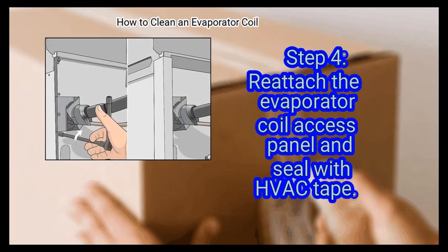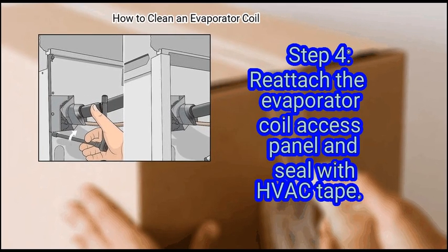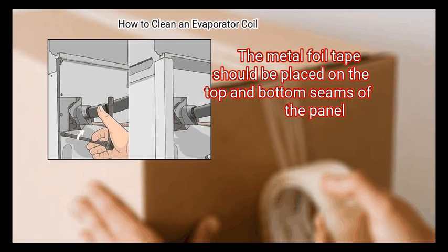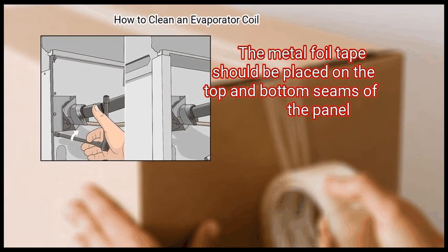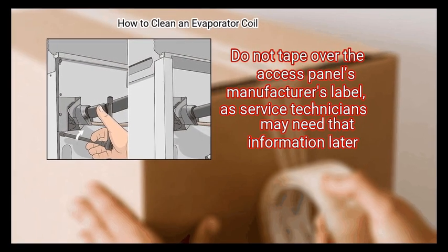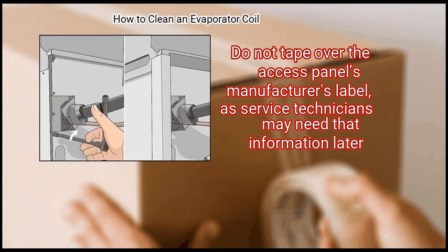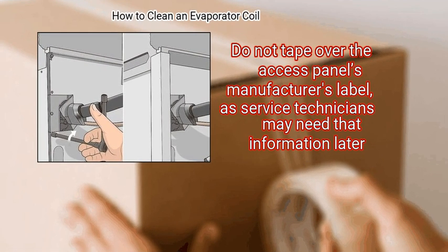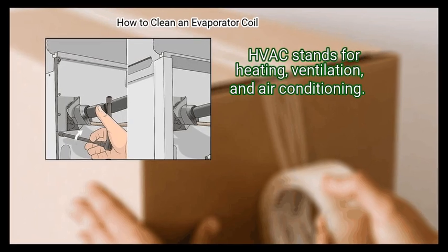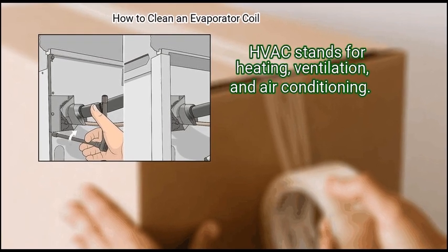Finally, reattach the evaporator coil access panel and seal with HVAC tape. The metal foil tape should be placed on the top and bottom seams of the panel. Do not tape over the access panel's manufacturer's label, as service technicians may need that information later. HVAC stands for heating, ventilation, and air conditioning.